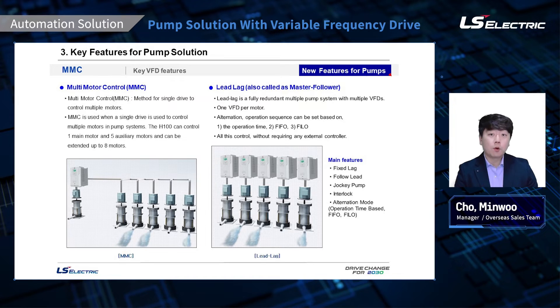Starting with MMC, multi-motor control. MMC is one drive with a motor connected to the output of the drive running at variable speed. The drive can have up to five auxiliary motors controlled as direct-on-line, or with the extension I/O option, up to eight auxiliary motors per drive. So MMC is one drive controlling multiple pumps, whereas lead-lag is a fully redundant pump system where multiple drives and pumps are coupled and used to operate at optimum efficiency. The system can be fully customized per application needs. If the master drive fails, the next drive will take over to maintain pressure and act as the new master drive. Pump operation sequence can be set based on operation time — first in, first out, or first in, last out.